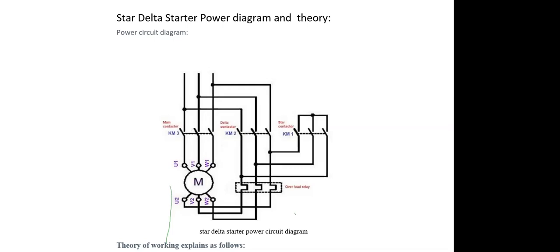One important thing here: if the phase sequence shown here, U1, U2, V1, V2, W1, W2, doesn't match, then it will not start properly. You may face a single phasing situation. U1 has to be connected with U2. If U1 is connected with V2, then this motor will not operate properly. I mean, it will not operate at all.